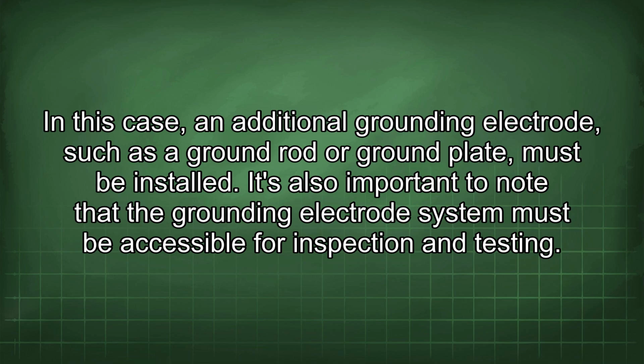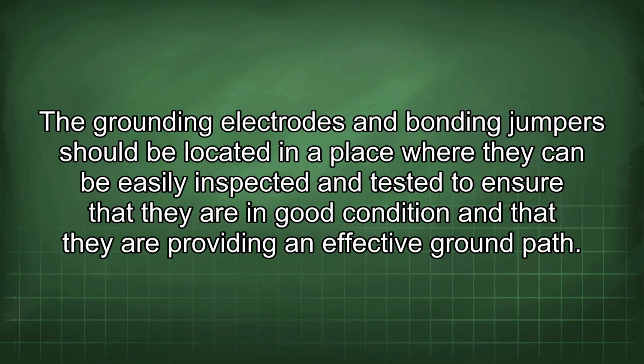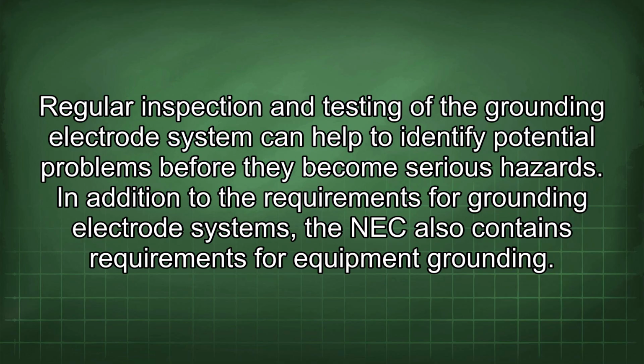It's also important to note that the grounding electrode system must be accessible for inspection and testing. The grounding electrodes and bonding jumper should be located in a place where they can be easily inspected and tested to ensure that they are in good condition and that they are providing an effective ground path. Regular inspection and testing of the grounding electrode system can help to identify potential problems before they become serious hazards.